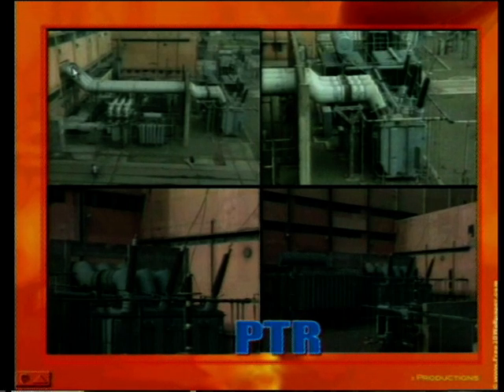Here you can see, for example, outside of the powerhouse, inside there is a generator which generates the electrical energy. At 21 kV, you can expect how large the size of the conductor, the diameter, would be. Then the power transformer takes this low voltage, high current and steps up to high voltage and low current. The same is connected to the bus bar. From the bus bar it is passed to different feeders.